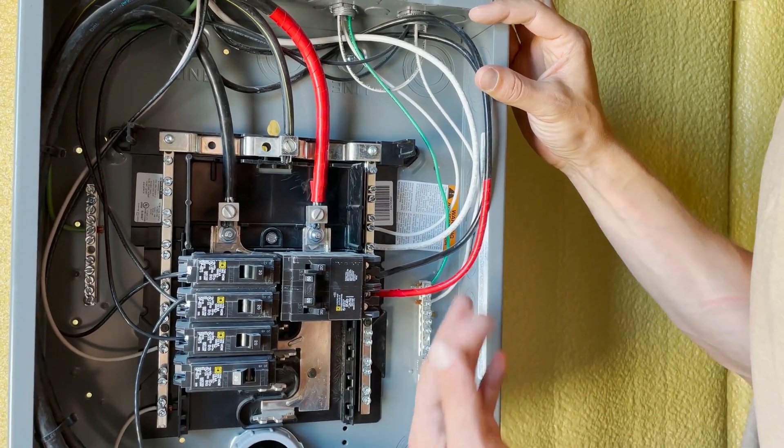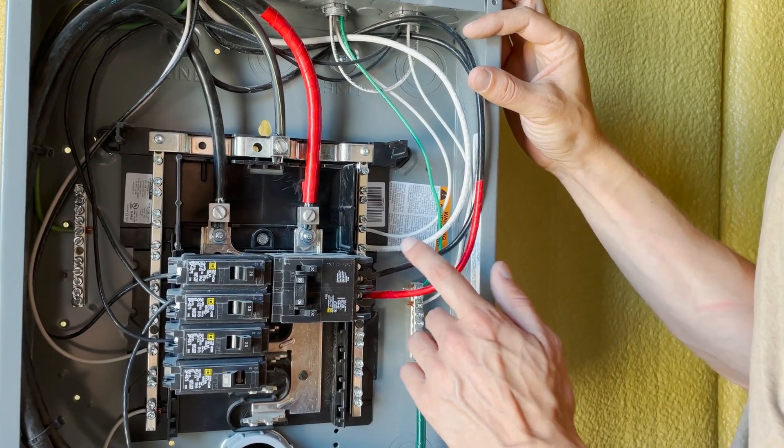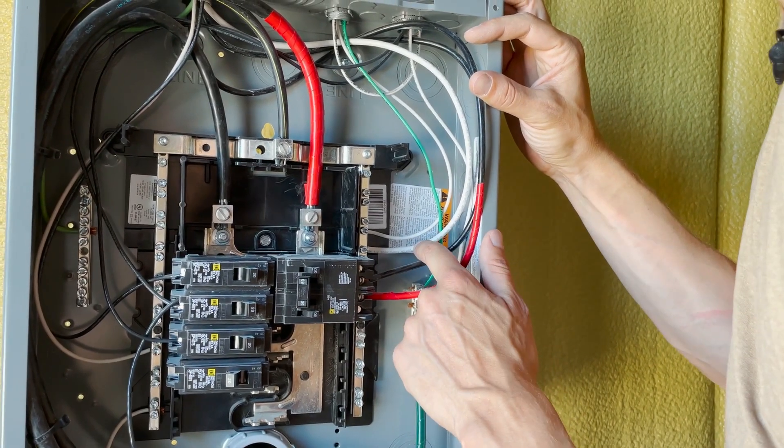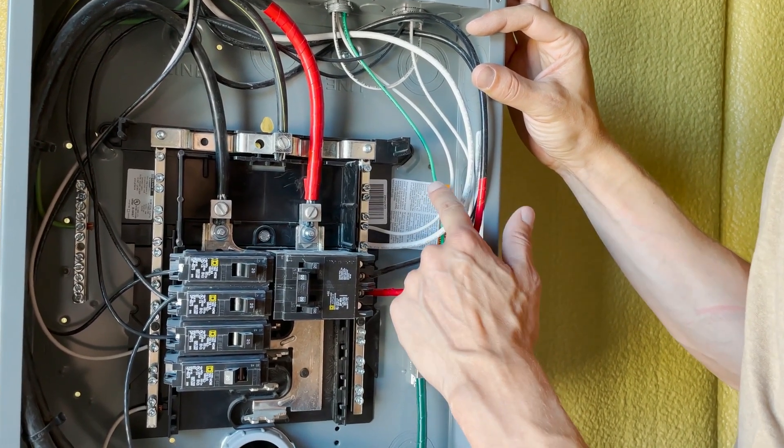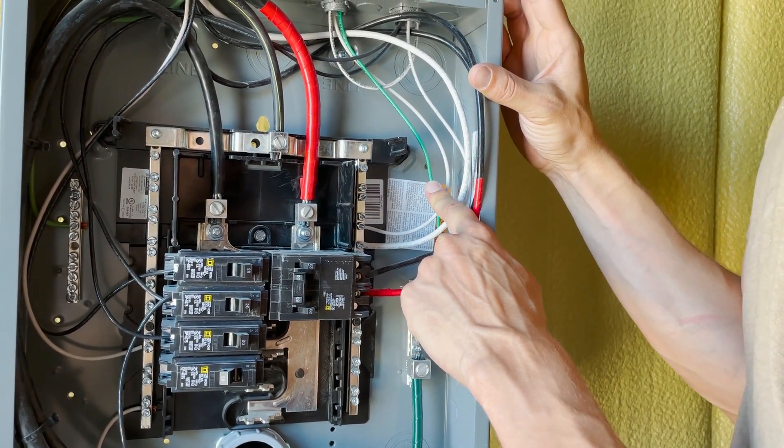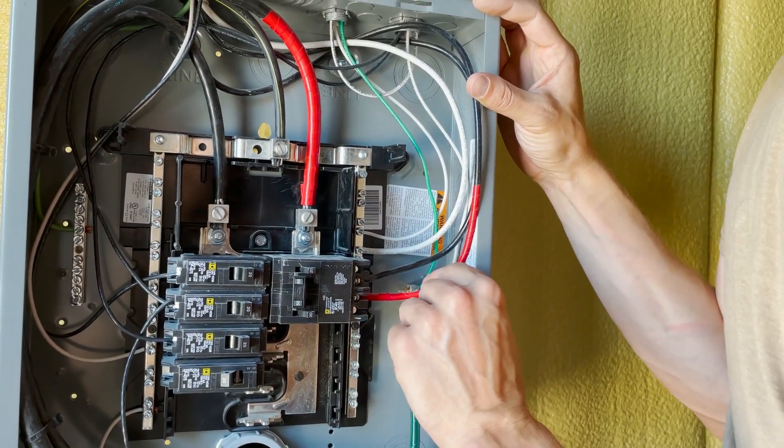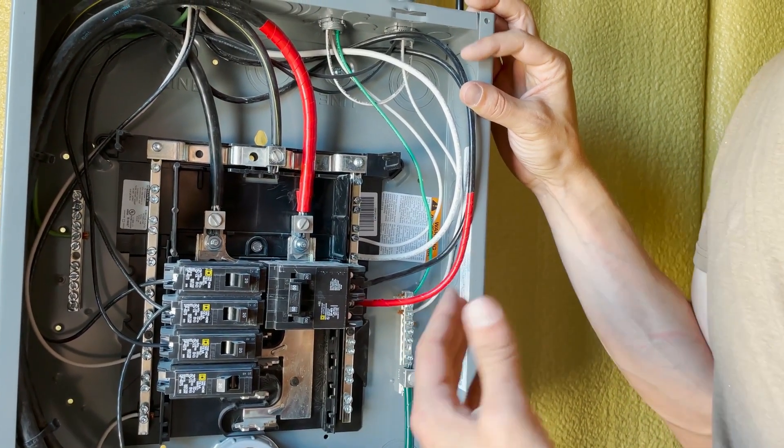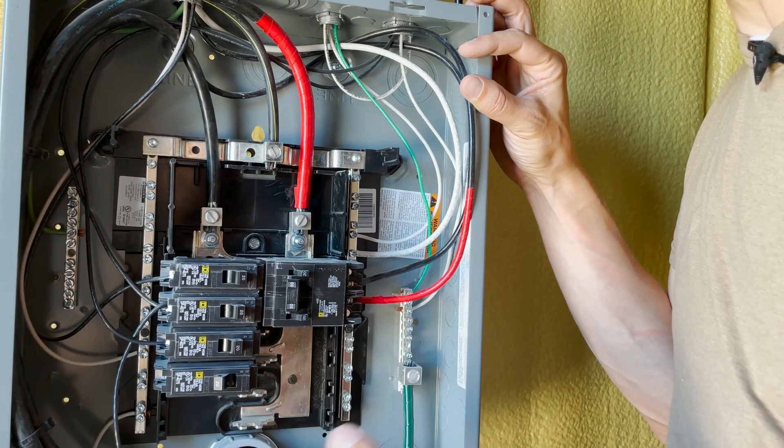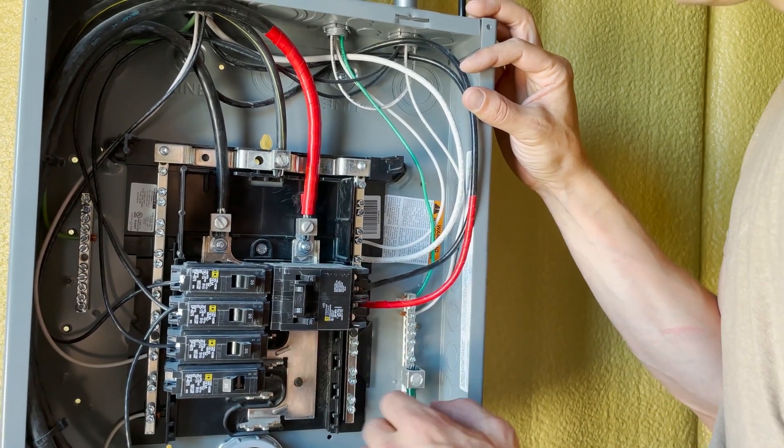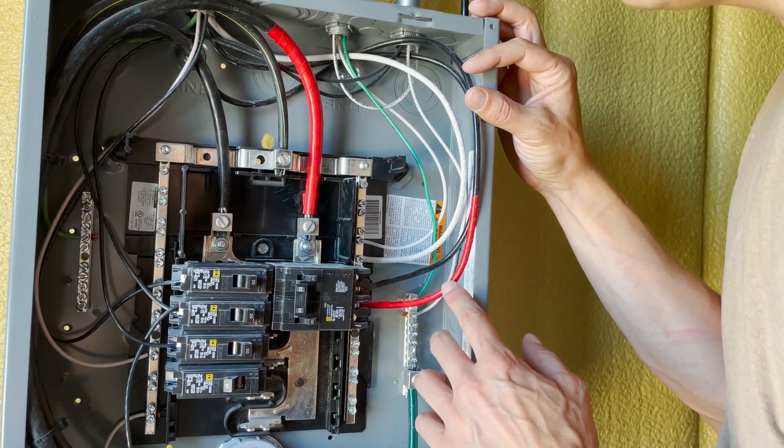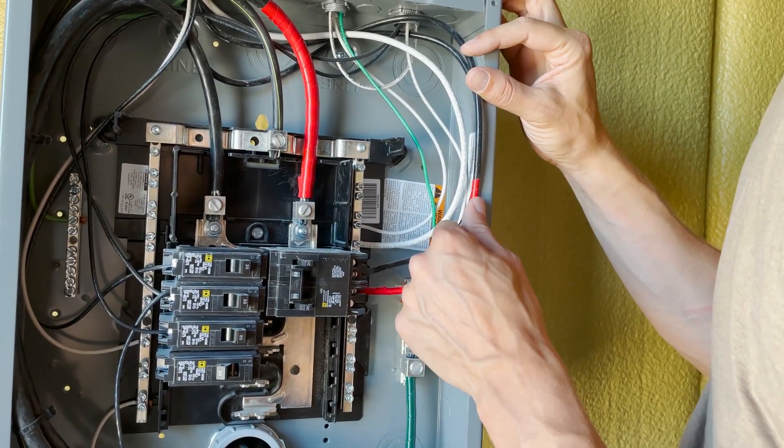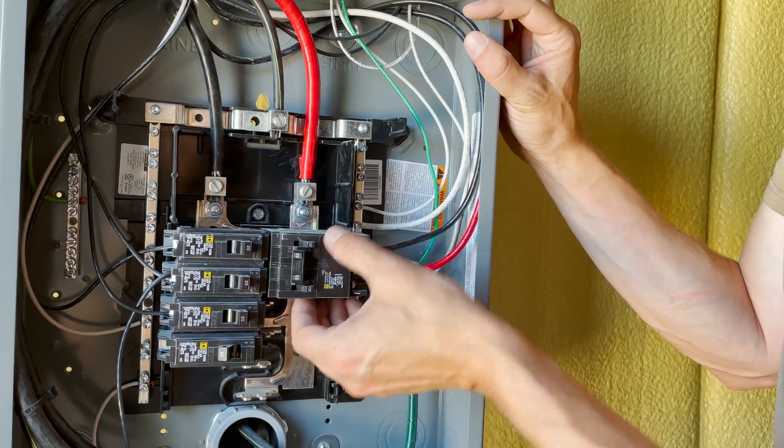When dealing with AC systems, black wire is hot, white wire is neutral, green or bare wire is ground—that safety ground—and then red wire is typically your other hot leg, but it can also be something else like a communication line. In this case, it gives us that second hot line.